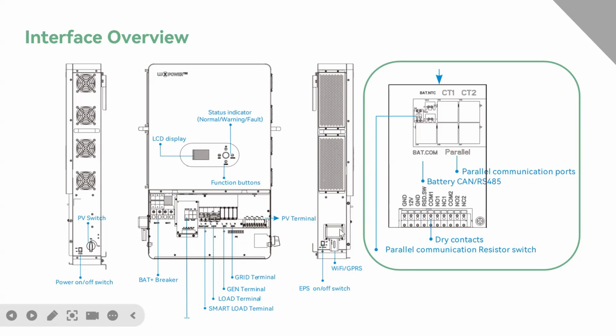And on the left side, there is the Wi-Fi dongle and the EPS on-off switch. And also there are 4 fans installed on the side of the SNA 12K. As for the communication ports, we have one for the CT, one for battery, both CAN and RS485, two parallel communication ports, and the dry contact port, for example for the generator start function. And this one is also used in the parallel system switch.